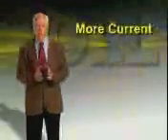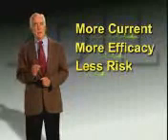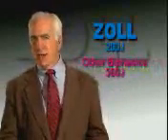You need the current. You want higher efficacy and lower risk. Zoll rectilinear biphasic has more current. Zoll delivers more current to high-impedance patients at 200 joules than other biphasic defibrillators, even those that escalate to 360 joules. How is that possible?